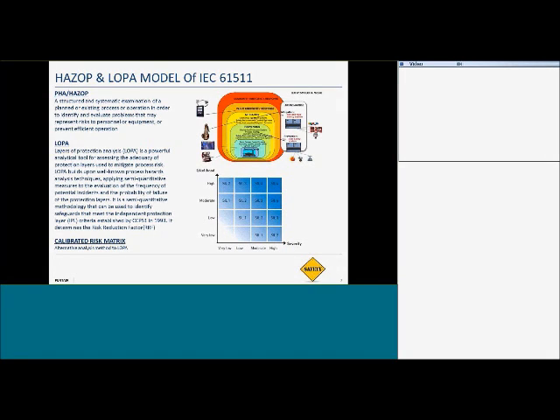And so this is how they're quickly determining SIL level. This group of people in the HAZOP may be sitting looking at a heat exchanger, for example, that's at the very back of the plant. There's not a lot of personnel at the back of the plant. They may determine that this has a very low level of likelihood and also a low level of severity, and so we may classify that as a SIL 1 application.